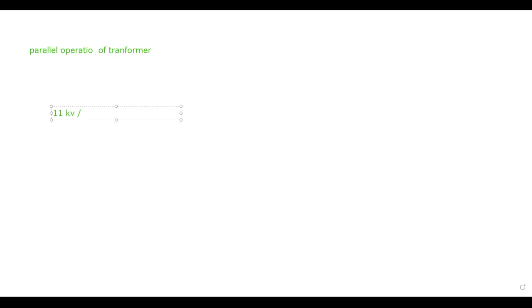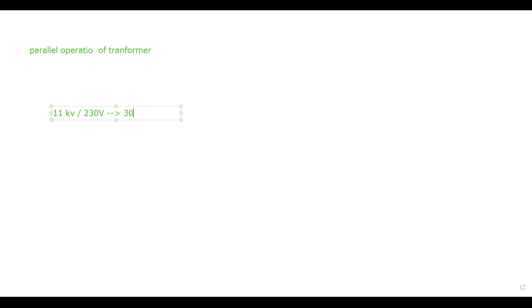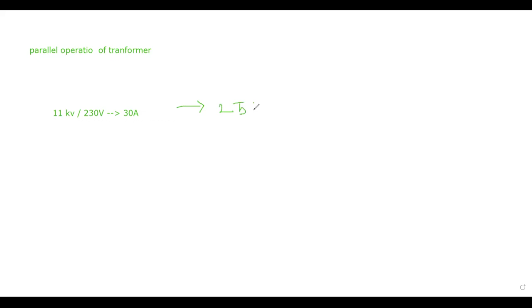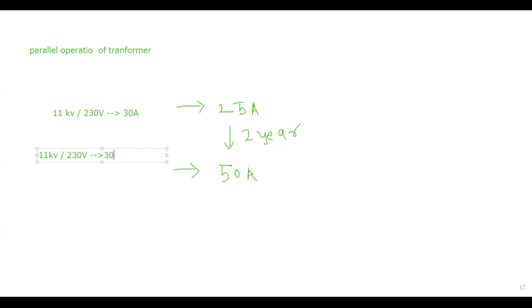Now, let's say I have one transformer which has a rating of 11 kV by 230 volt, and current rating is 30 ampere. Right now, the load connected to this transformer is 25 ampere. Now, suddenly, within 2 years, this load has increased to 50 ampere. Now, what should I do? I have two options right now. First one is I can connect another 11 kV by 230 volt transformer, with the same current rating of 30 ampere, in parallel. This is option number 1, which is on your screen.